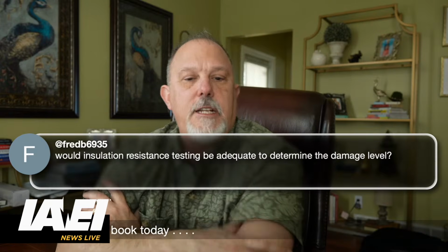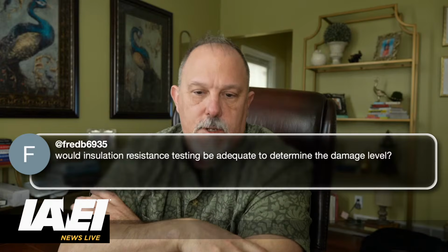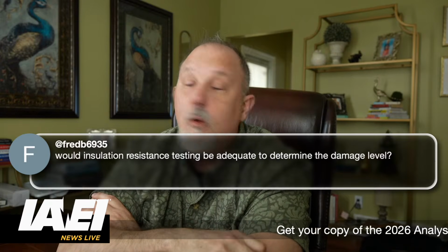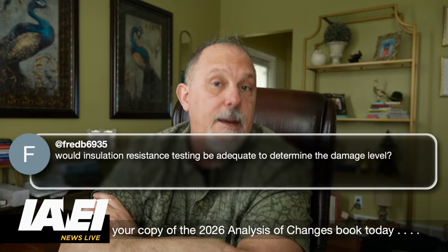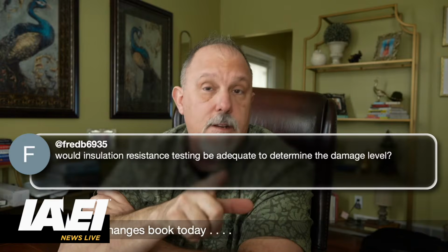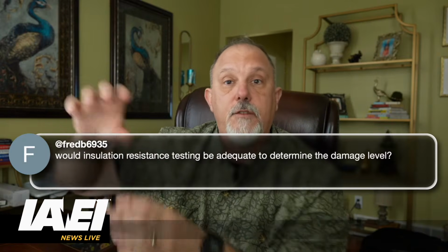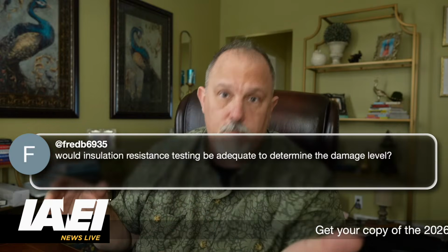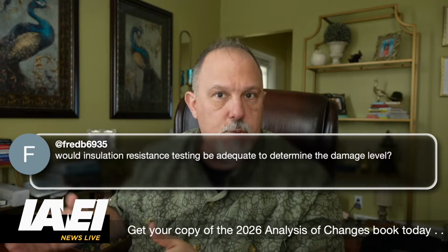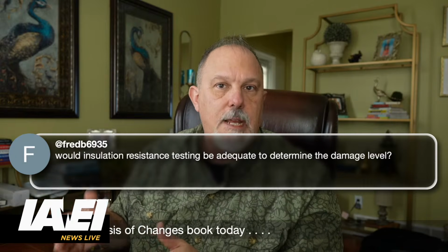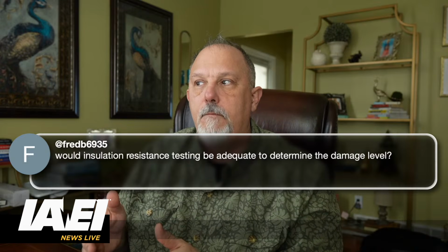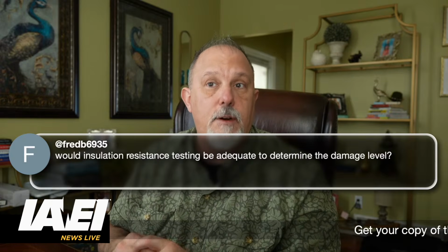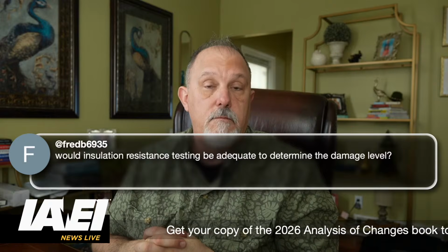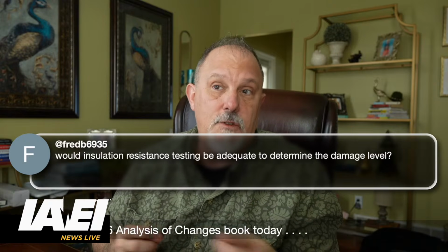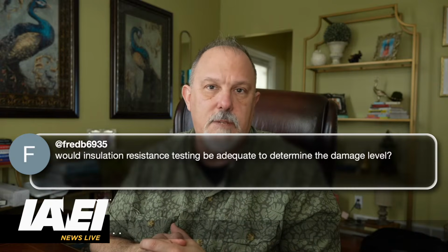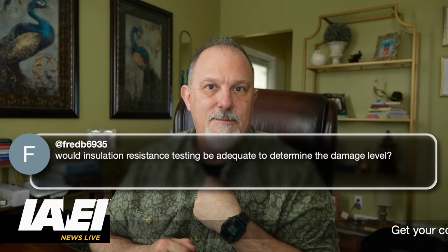Freddie B asks, would insulation resistance testing be adequate to determine the damage level? So you're talking like high pot testing. I'd say that's a very good approach. Now you've got to be careful with that, because you've got to disconnect things you could otherwise damage. Follow the right procedures when doing high pot testing or insulation resistance testing, so that you don't damage equipment. But yeah, that very well could be, in my opinion, a great start, especially for conductors. If you do insulation testing on a conductor, you know that conductor has some integrity. That would be my take, but you know.